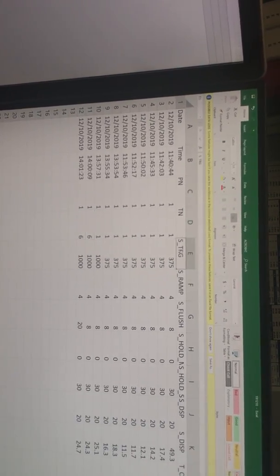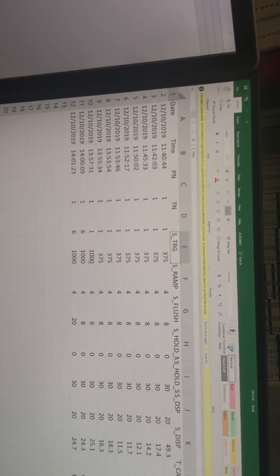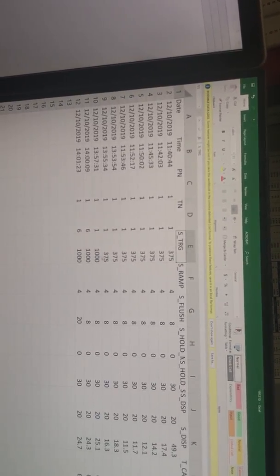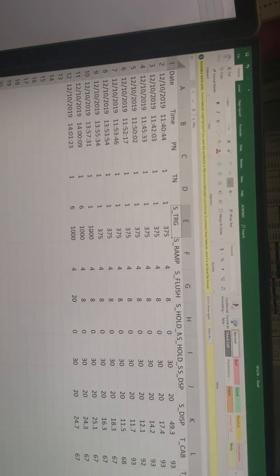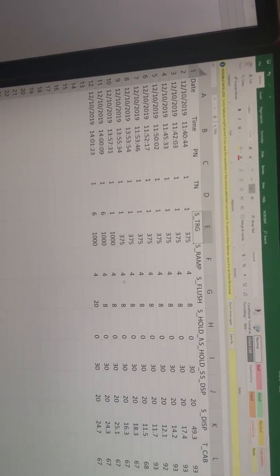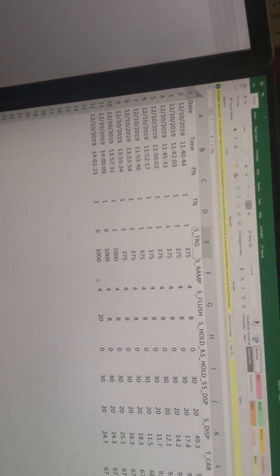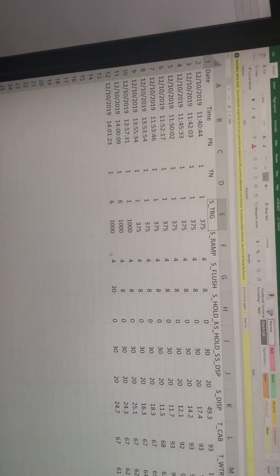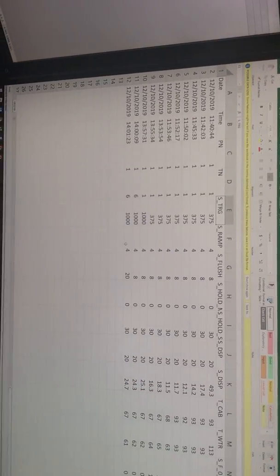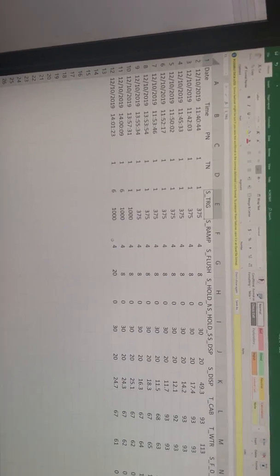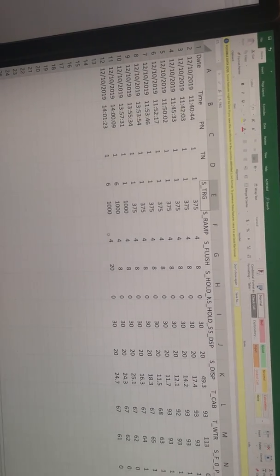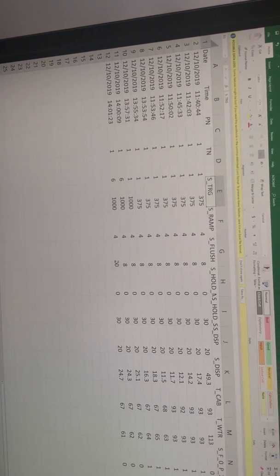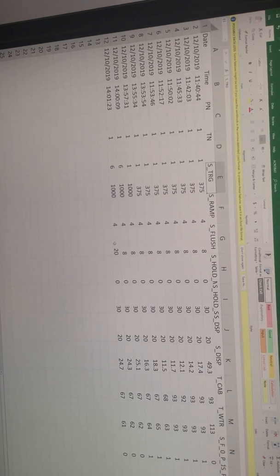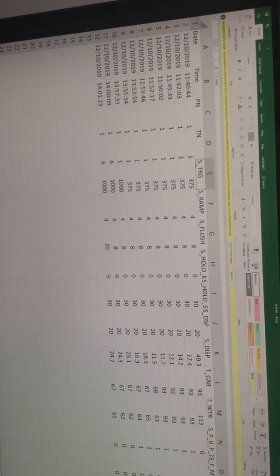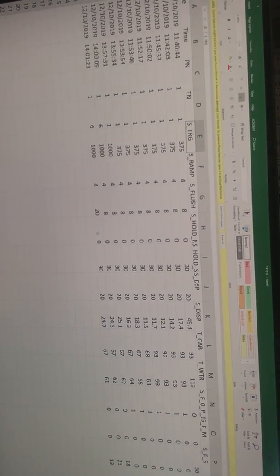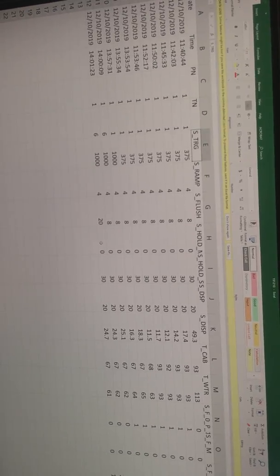And so then you have your target value. We set the pressures. We were doing 375s, now we went to 1,000. We did 3 1,000-pound tests. We did it in 4 seconds, which actually is a bit fast. You really shouldn't go faster than a second per 100, so it should have been a 10-second ramp. Shame on us. Then we flushed it. We decided we're going to flush it more aggressively, so we flushed it 20 seconds. And once we got to 1,000 pounds, we went right back down, no hold.